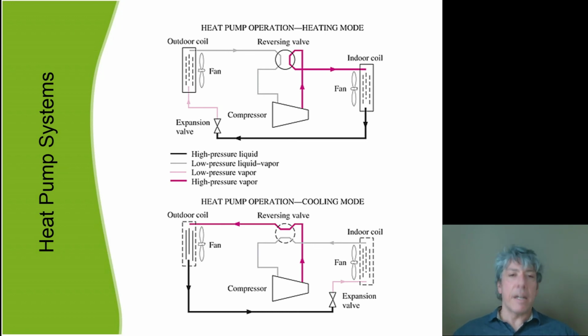Now you can say, well, there's no heat outside. Yes, there is, because what you really mean by heat is thermal energy, and there is still thermal energy outside. The air molecules are still zipping around, right? They still have energy, and we can extract some of that energy and use it to pump up its quality, in other words its temperature, and use it in the home. So what the outdoor coil does is it takes this mixture of vapor and liquid and it completes the boiling process. And so what happens is the outdoor air gives enough energy to the refrigerant to boil off the remaining liquid, which all goes to vapor and then goes through that upper gray line back to the compressor to complete the cycle.